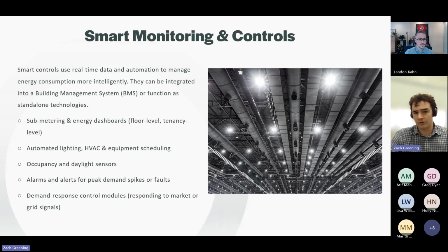The benefits go beyond just energy savings though, and we'll look at equipment longevity in a little bit, but these smart controls can really help by detecting system inefficiencies. So you've got a fan running 24/7 when it shouldn't be running 24/7. You're able to identify that and address that through things like these management systems. It also prevents short cycling and overuse, especially for chillers and compressors, and will help reduce your maintenance costs through early fault detection, as opposed to something having a catastrophic failure and needing replacement. We can see it's drawing a bit more than it should. We should have it checked out and maybe give it a service.